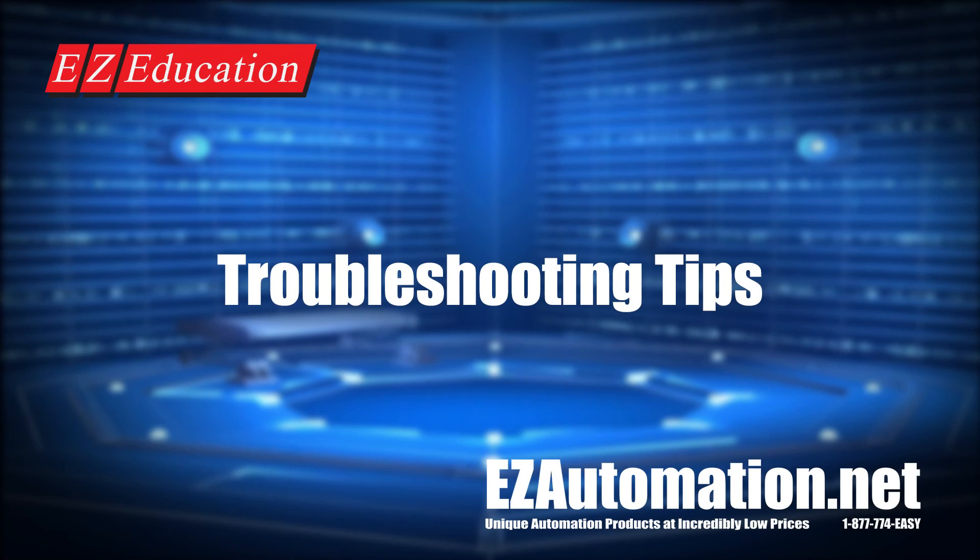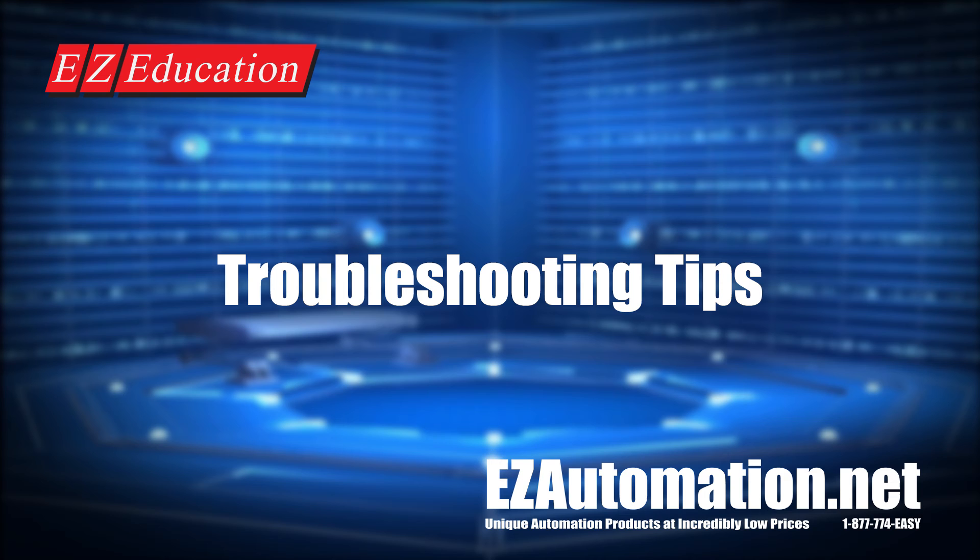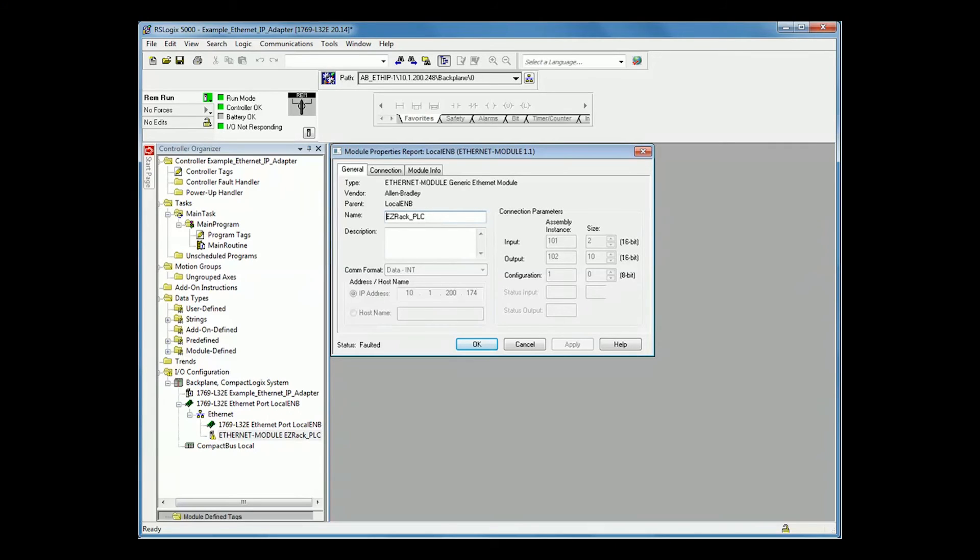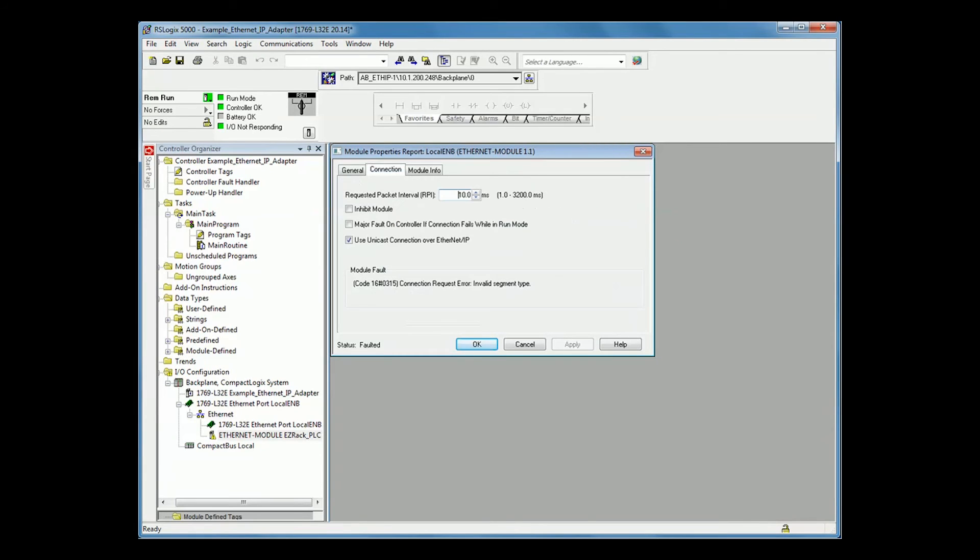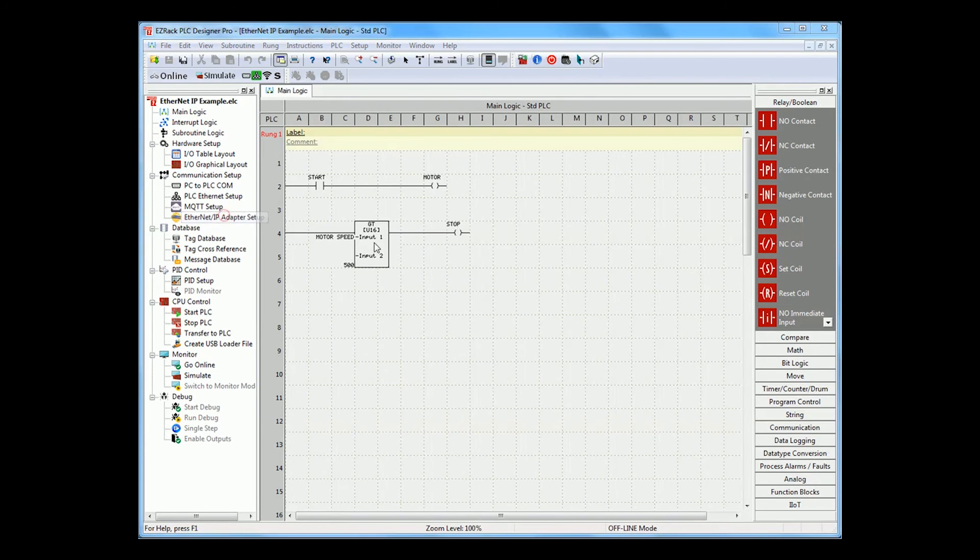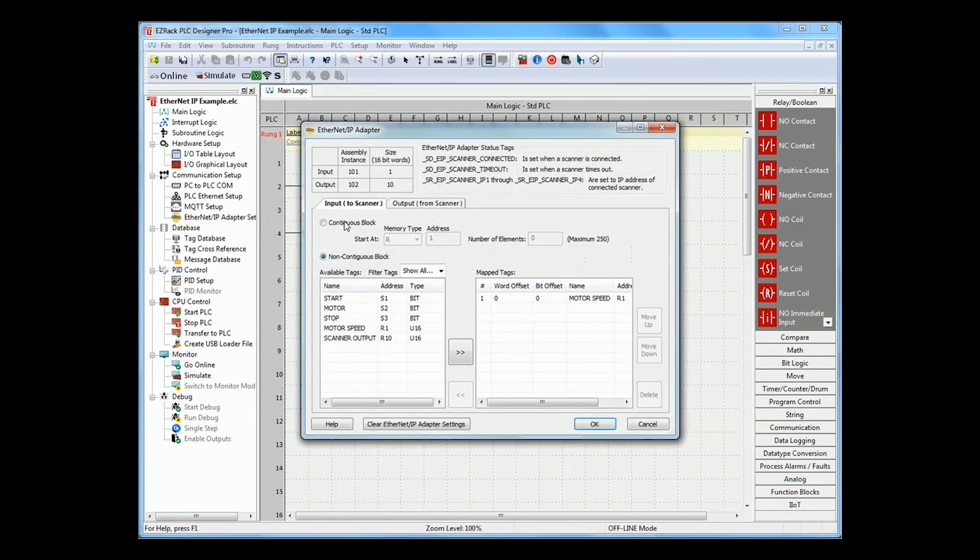Now, some quick troubleshooting tips. There are two major errors that can be encountered when setting up the EZRack PLC as an adapter. The first major error you can encounter is if your module fault is connection request error invalid segment. This happens if your connection parameters on your CompactLogix do not match the ones in your EZRack PLC. So, if you see here, I am off by 1 in the input size.